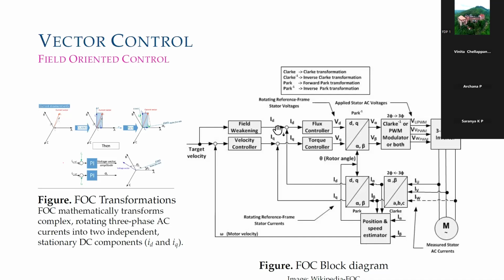So that is why it is said to be independent control. We have flux control as well as torque control. In the outer loop, we have the velocity controller or speed controller. This velocity controller generates the reference currents for the whole system, and then we can control the motor using the three-phase inverter. So this is the basic idea of field-oriented control.